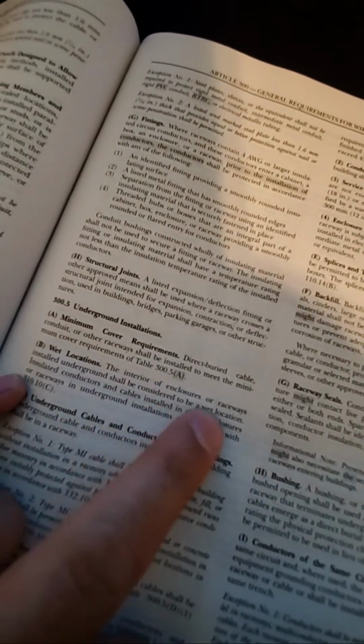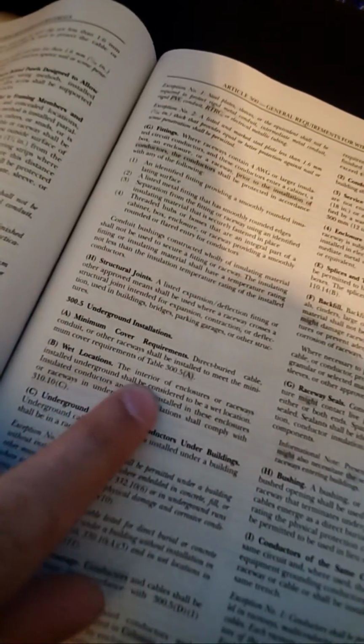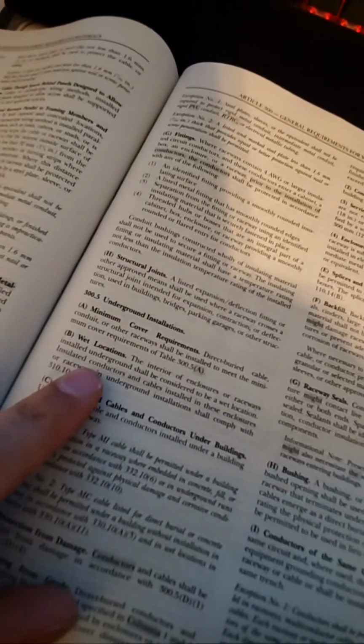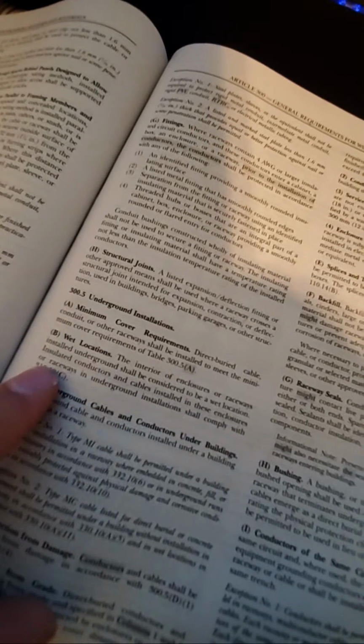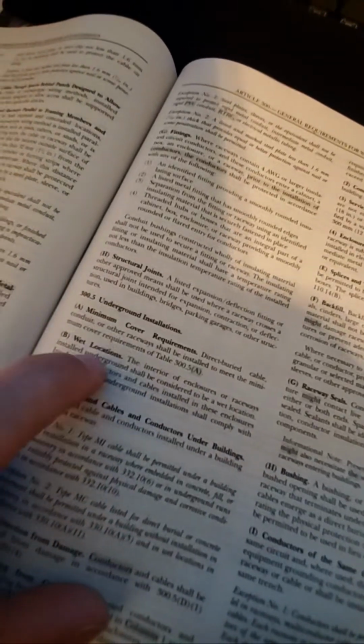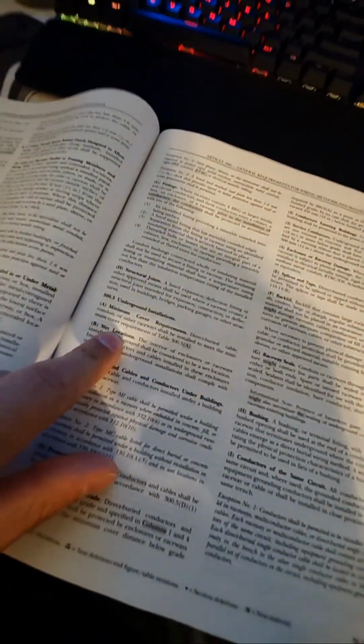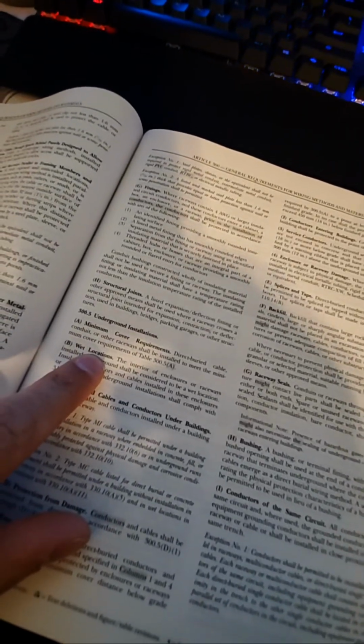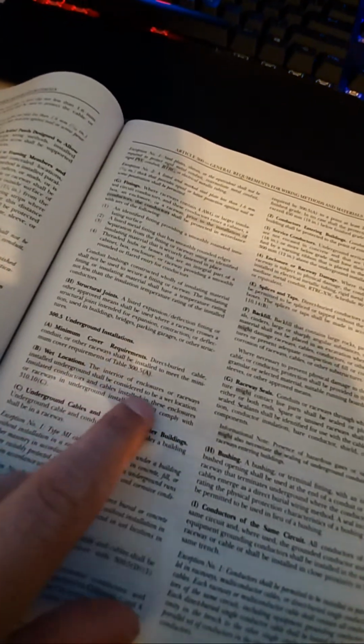Wet locations, right? This is a hot item on YouTube, right? The interior of the enclosure or raceway installed shall be considered a wet location. Insulated conductors and cables installed in these enclosures or raceways and underground installations shall comply. If you go to your raceways, it says this a lot. It says wherever you install the raceway, even if it's PVC, which would normally be dry, if you install PVC on a roof, the wire, the interior of the raceway, that's what it says there, interior of the enclosures or raceways are considered wet wherever they're installed.